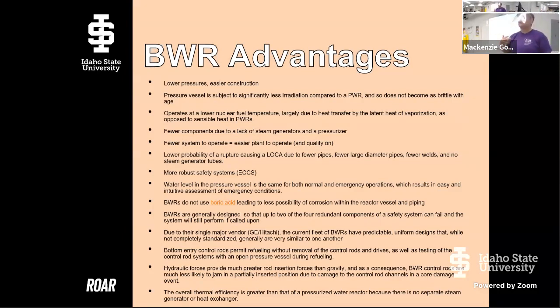Your likelihood of leaking reactor coolant out of your reactor is lower because you have fewer pipes, since you don't need that intermediate system with the steam generator. You don't need as many large diameter pipes because you're pumping steam instead of water, and gases completely fill whatever vessel they're in. With less piping and smaller pipes, you don't have to make as many welds. Welds are where we have difficulties at nuclear power plants because you can have corrosion issues and strength issues. They're difficult, so having less of them is good.